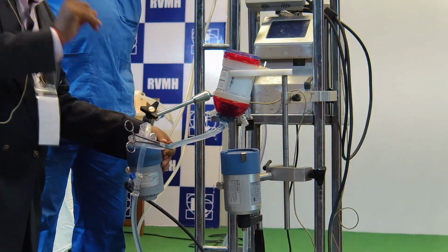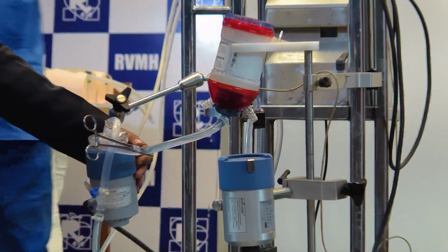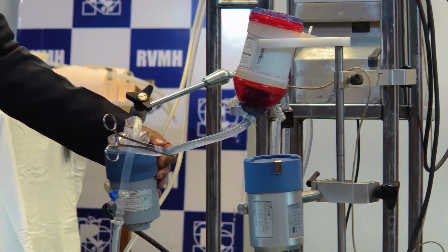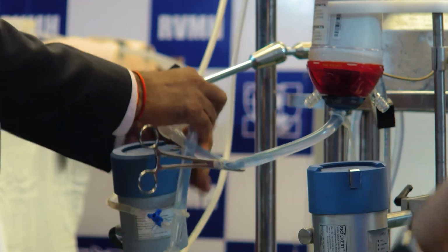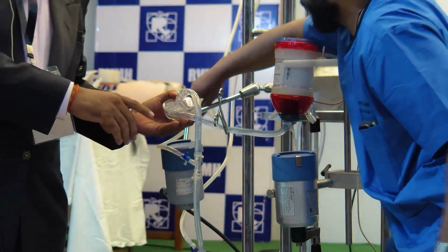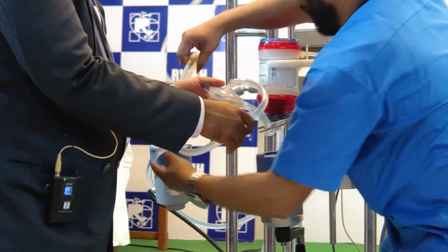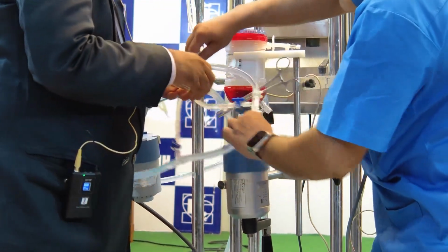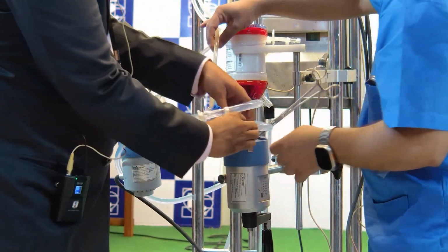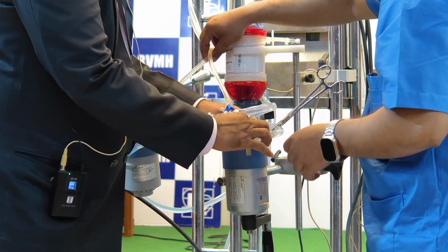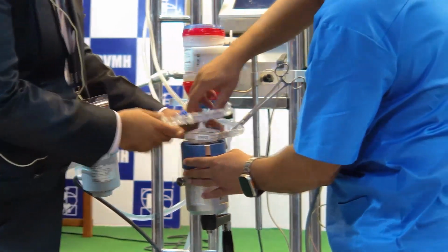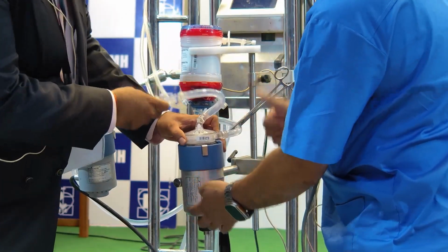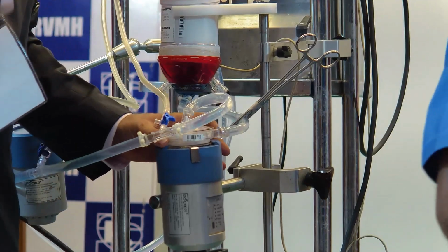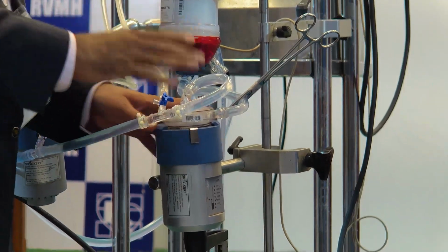Remember, each pump has a locking mechanism, so you should know the locking mechanism of your pump. Take the pump out, call for help, ask somebody to assist you, since this is an emergency situation that has occurred suddenly. Put the pump on the hand crank. Can you hear that voice? That is important, it means it got locked.